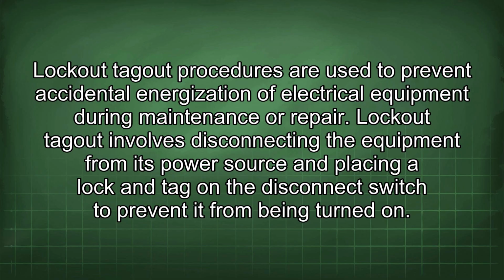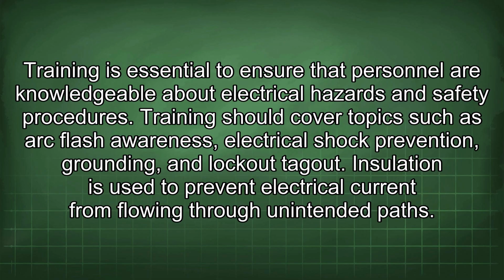Lockout-tagout procedures are used to prevent accidental energization of electrical equipment during maintenance or repair. Lockout-tagout involves disconnecting the equipment from its power source and placing a lock and tag on the disconnect switch to prevent it from being turned on. Training is essential to ensure that personnel are knowledgeable about electrical hazards and safety procedures. Training should cover topics such as arc flash awareness, electrical shock prevention, grounding, and lockout-tagout.